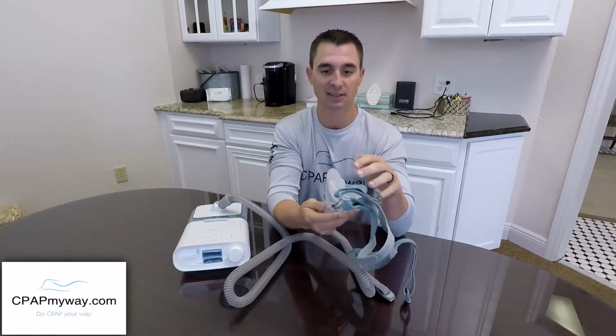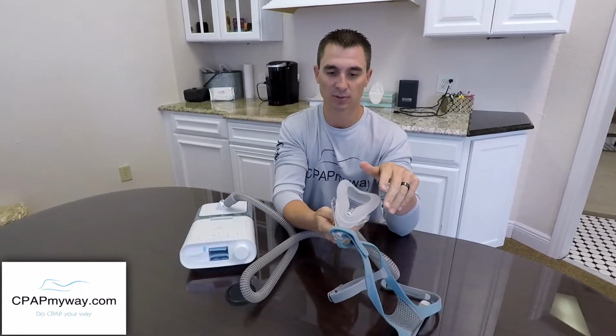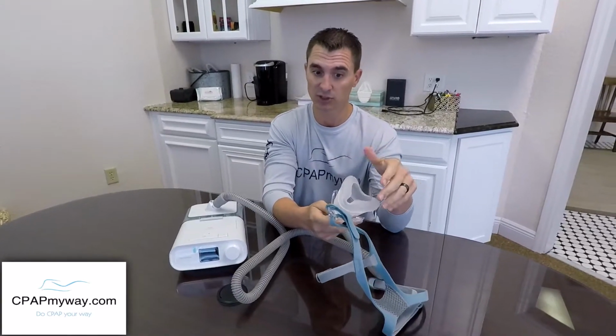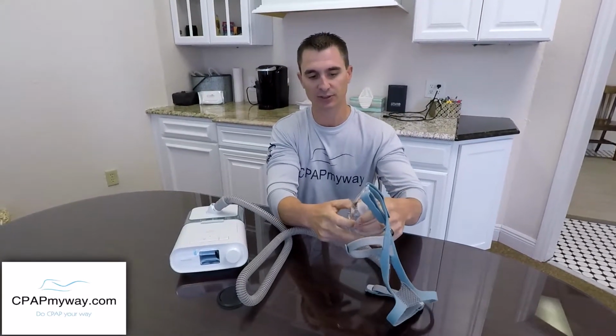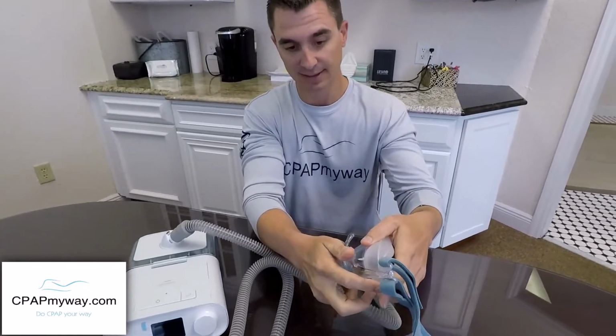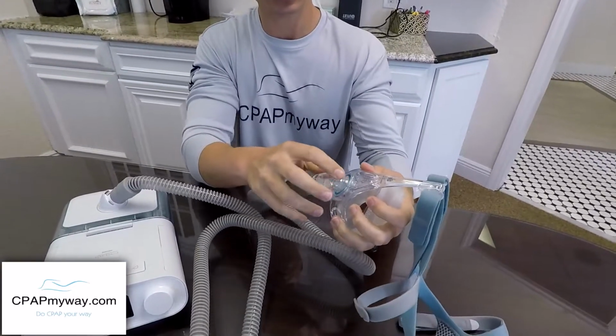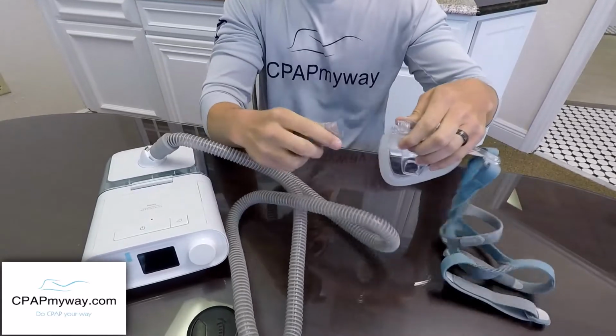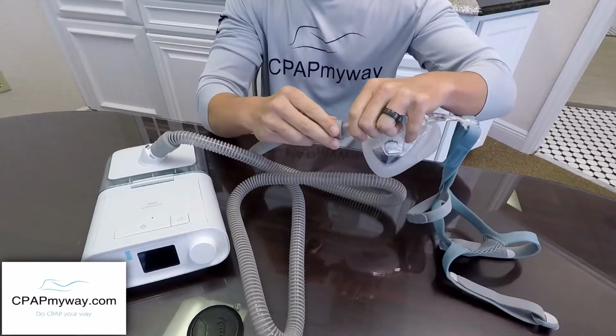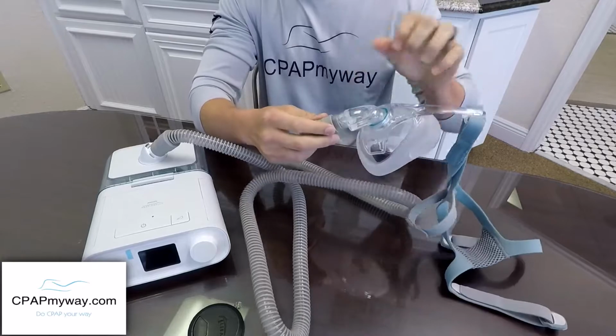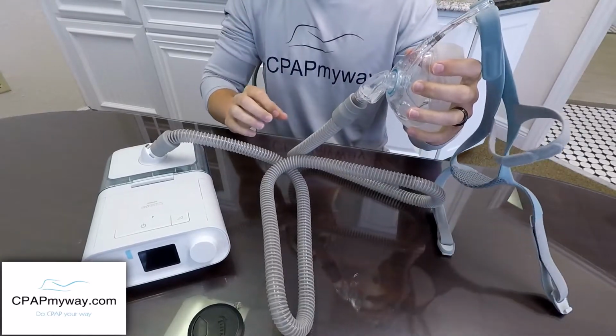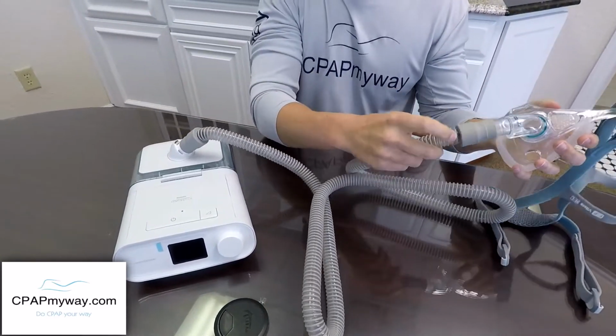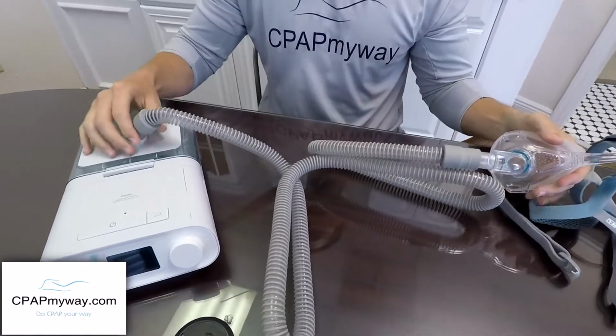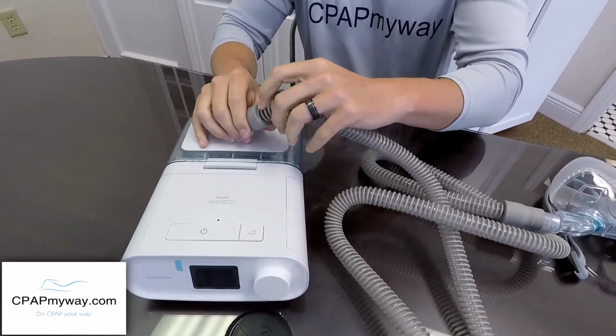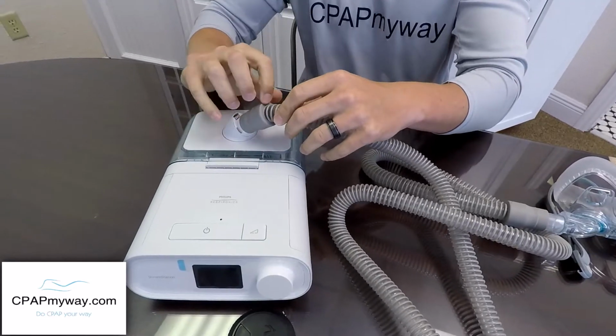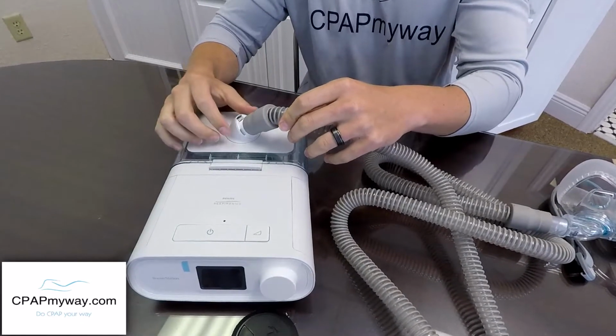Start right with the seal. Make sure there are no tears or issues with the seal. If it's been a while, replace your seal. Next, make sure that your seal is attached correctly to the mask, that you don't have any issues with the connection point there, and that your quick connect and CPAP tube are all nice and tight and connected correctly. Some of those can get crooked on different models. Trace it back, and make sure in all the little joints you don't have any breaks. It's very common on these, right up against the rubber cuff, to have some cracks or tears in that tube.